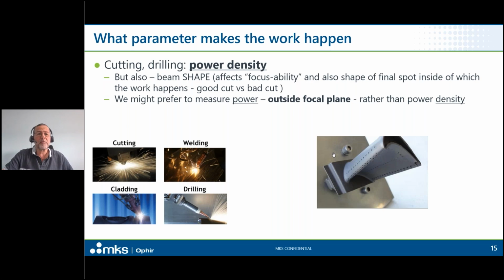We very often might prefer, rather than directly measuring power density, and there are tools that do that, to just measure the power, because it's usually easier, and we're going to absolutely want to do that outside the focal plane. We don't want to measure inside the focus if we don't have to, because it's the same number of watts or joules outside focus as inside focus, but inside focus is where the power density is high enough to cut, drill, melt, vaporize, and I could just as easily end up zapping my power measurement instrument, and I don't want to do that.